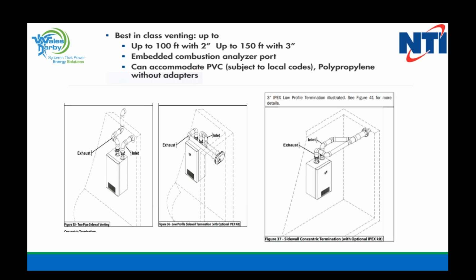Now, when it comes to venting, you've got a lot of different options. Again, up to 100 feet with 2-inch, up to 150 feet with 3-inch. We can do PVC, we can do poly, all right? We can do CPVC. Again, you're going to get that 5.5 inches of straight CPVC that must be installed on the exhaust. Then after that, you can adapt to whatever your venting material is going to be.